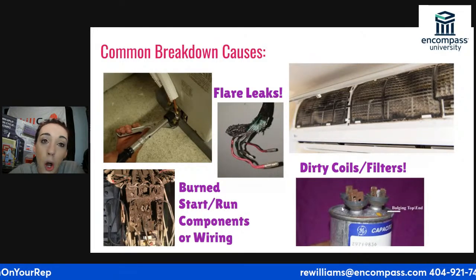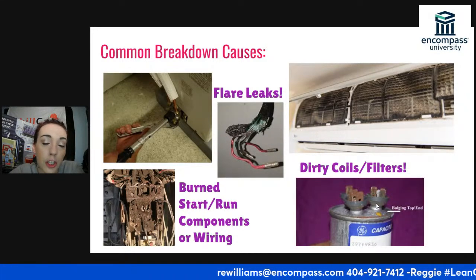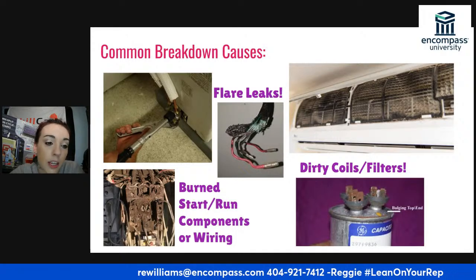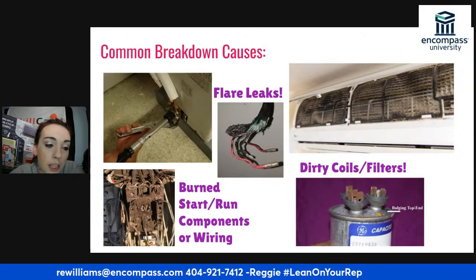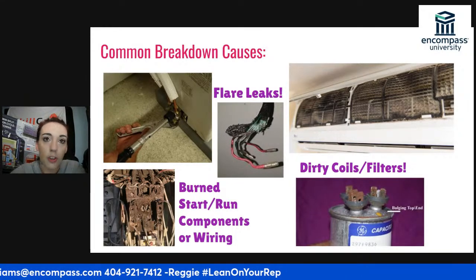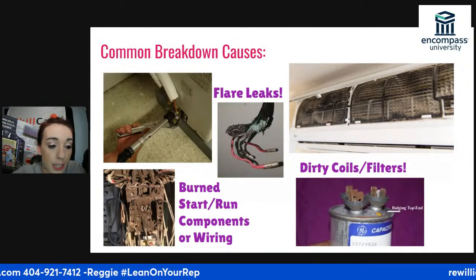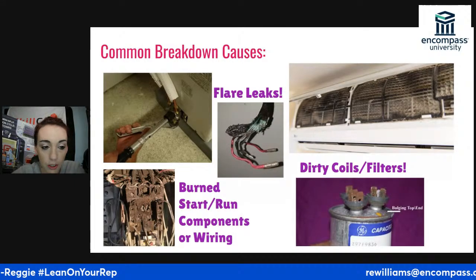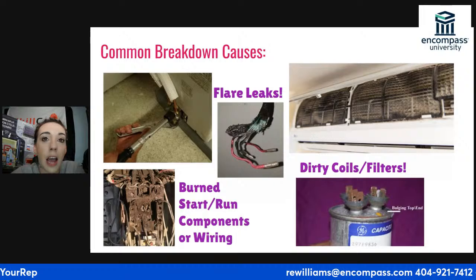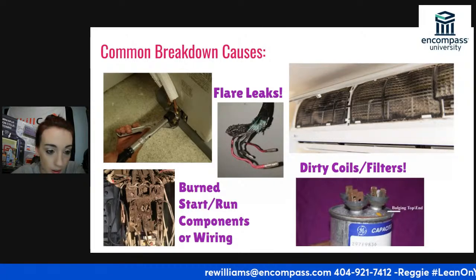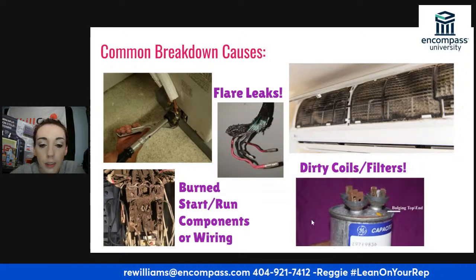If there are no obvious signs after you've discharged the capacitor, you can test the capacitor in microfarads, and you'll usually have to be within plus or minus 5. So if it calls for 35 and you have a 30, your capacitor is good. If it calls for 35 and you have 45, it's not good. So yeah, test your capacitors.